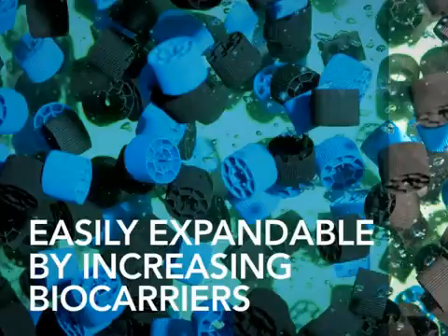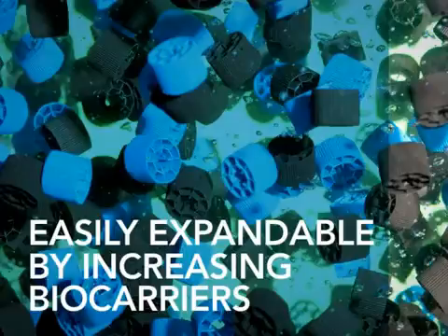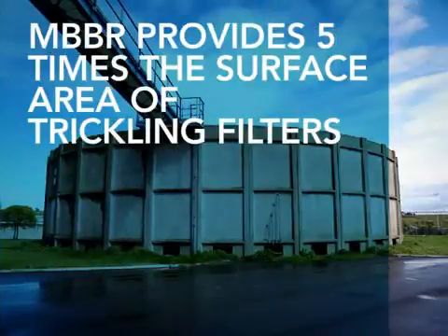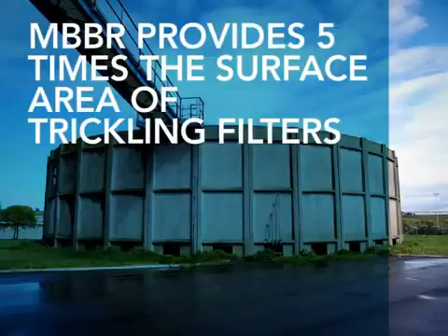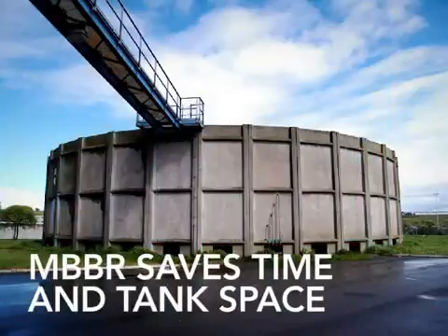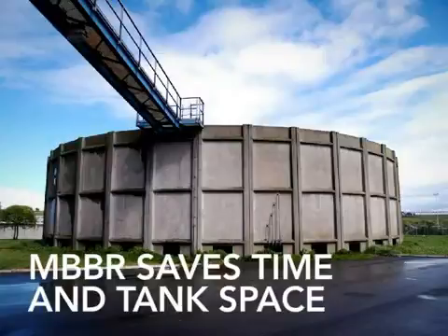70% by volume. At equal levels of BOD removal, HeadWorks Bio's MBBR provides up to 5 times the biofilm surface area of a trickling filter, using less than a quarter of the reactor volume. When compared to an activated sludge extended aeration process, MBBR saves time as well as tank space.